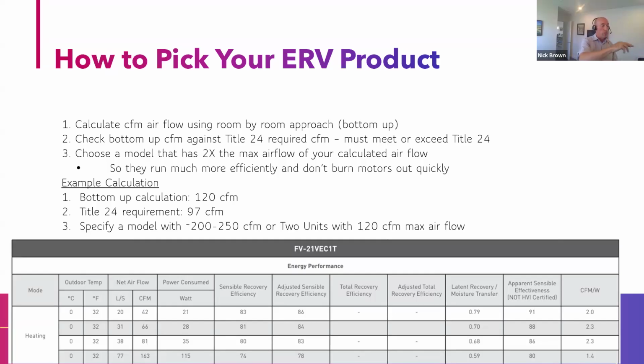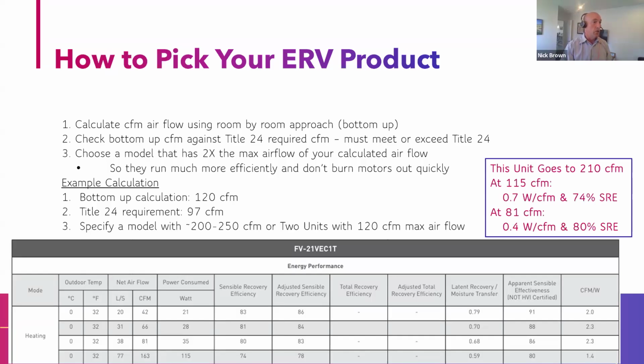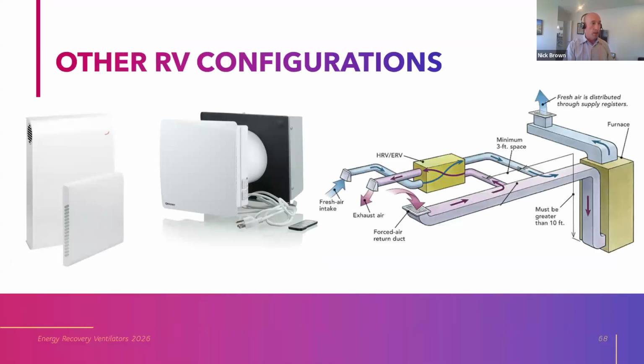As you can see from this chart here from a major manufacturer, it's actually showing CFMs per watt, and it's best in those mid-range airflows. It's much less efficient when you get up to 163 CFM in this example. So in Scott's example, he got 120 CFM with his bottom-up approach. Title 24 would have asked for 97. So you specify a model with 200 to 250 CFM, somewhere in there, or 2 units with 120 each. Notice that at 115 CFM, this unit works less efficiently, higher watts per CFM, and lower recovery effectiveness than it does in that mid-range. And that's why Scott uses that as a best practice.